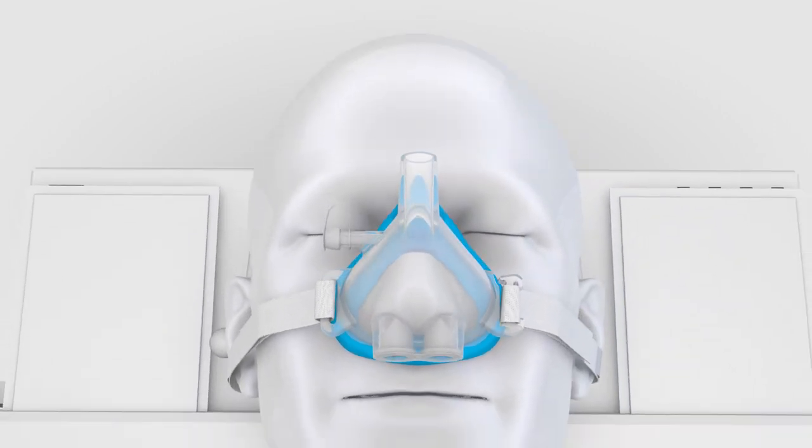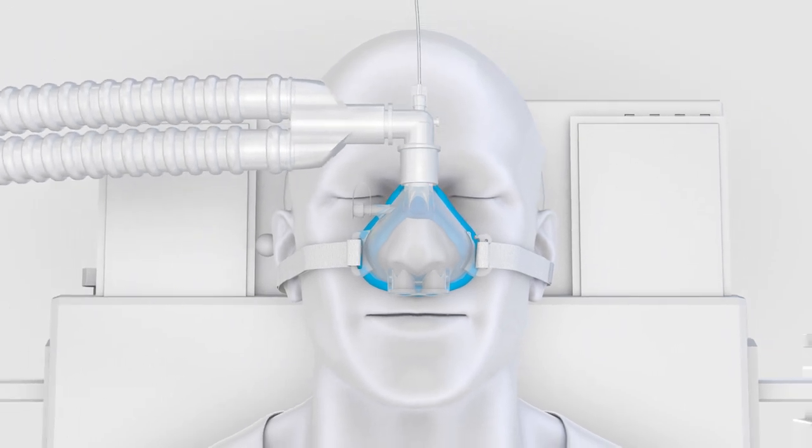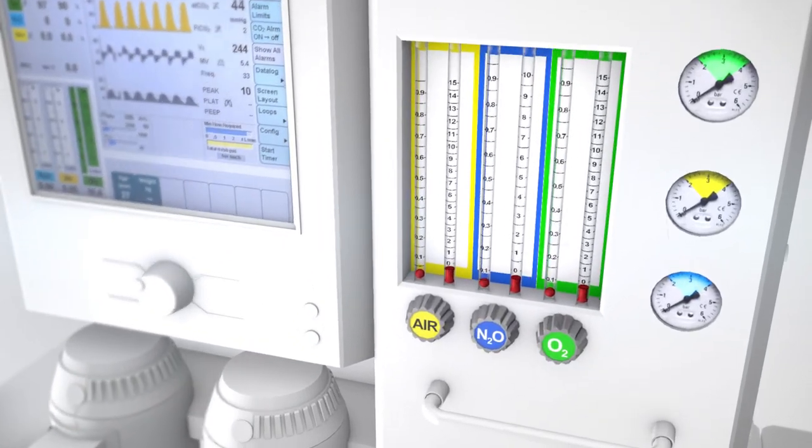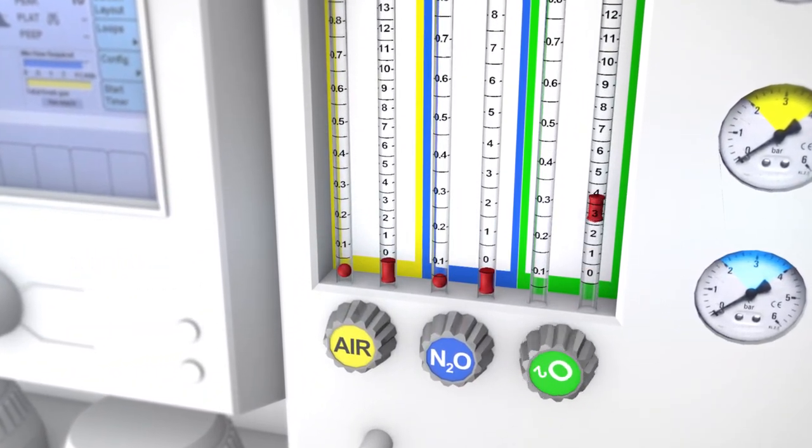Inside the operating room, connect the circuit from the anesthesia machine to the SuperNova device using the circuit port, remembering to have adequate fresh gas flowing and the machine set to spontaneous mode.